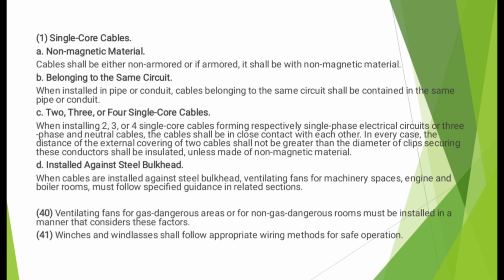In every case, the distance of external covering of two cables shall not be greater than the diameter of clips securing the conductor, which shall be insulated unless made of non-magnetic material. Installed against steel bulkhead: when cables are installed against steel bulkhead, ventilating fans for machinery spaces, engine, and boiler rooms must follow specified guidance in related sections. Ventilating fans for gas dangerous areas or for non-gas dangerous rooms must be installed in a manner that considers these factors. Winches and windlasses shall follow appropriate wiring methods for safe operation.